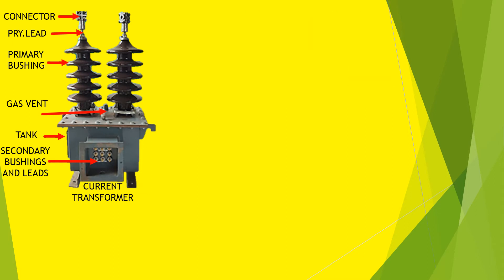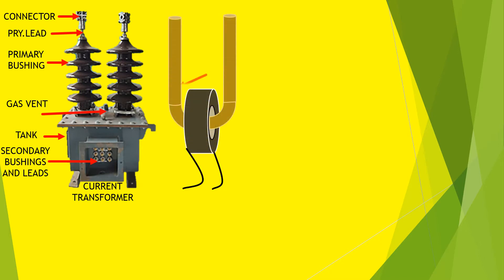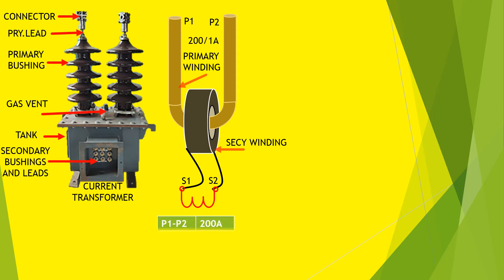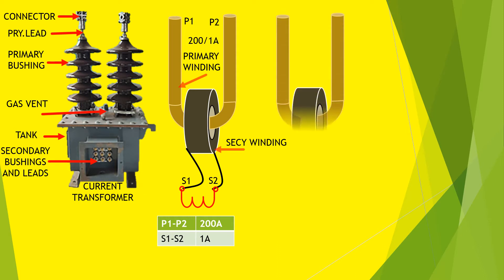Now see the drawings of the current transformer winding and cores. P1 and P2 are its primary winding connection leads. It has only one core at the secondary side having secondary leads S1 and S2. The rating is 200/1 ampere, which means if current inflows 200 ampere through the primary, then secondary current will be 1 ampere.